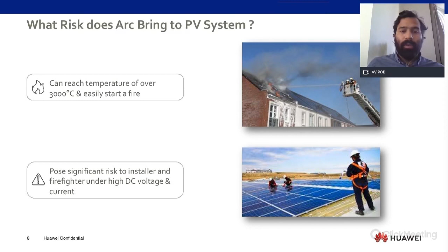And just to give you an example, this is a famous case. Some of you might have heard that between 2012 and 2018, the American supermarket franchise Walmart experienced fires on the roof in some of its stores, and this was identified as a problem with the PV. The main reason was poor installation. After some inspection, they found loose connections or cables not securely tied. They were just hanging around. So these are some potential installation hazards that led to around seven fires between 2012 and 2018. And as you can see, this presents a significant hazard because these are places where usually people are around.